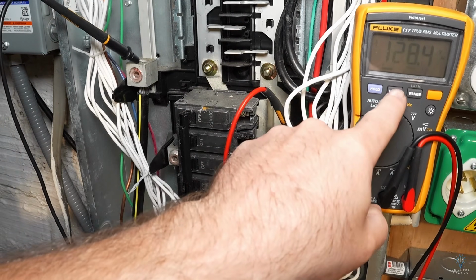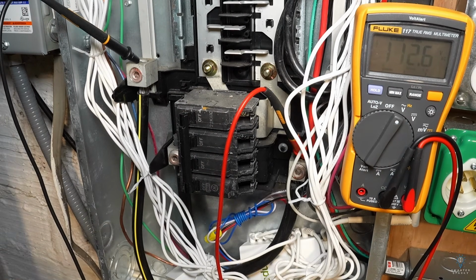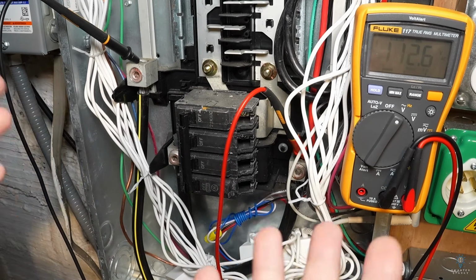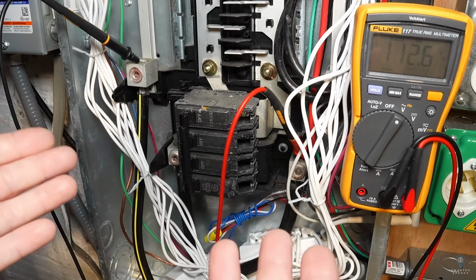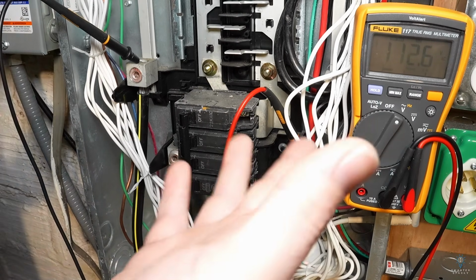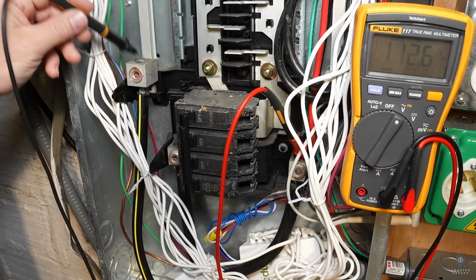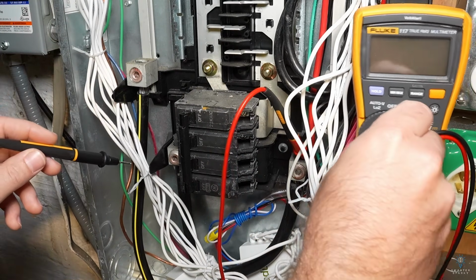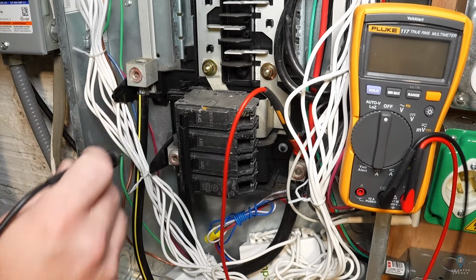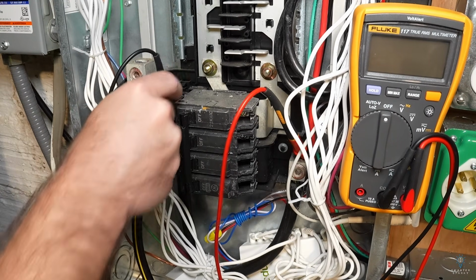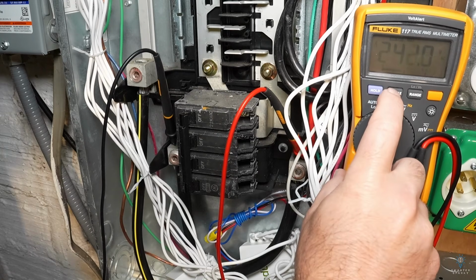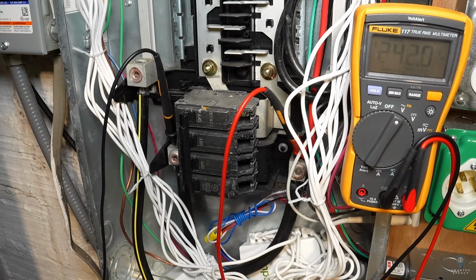So our max is 128 and our minimum is 112. So we've got a 16 volt swing there in just 2-3 minutes. That very much screams to me that we've got a neutral issue. Now let's just do the same measurement from line to line. I'm gonna shut this off and reset it here. So I'm gonna shove this probe into the other line, and let's set to min max and read our live values. And I have a sneaking suspicion that we're not gonna see hardly any deviation here.